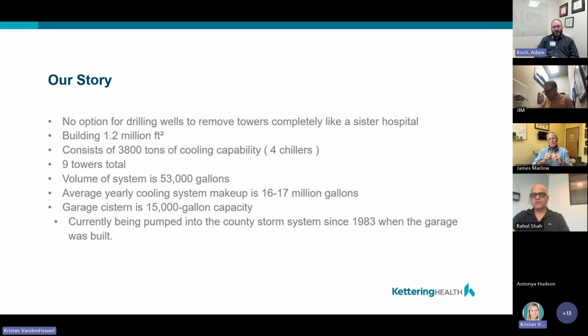We have 3800 tons of cooling capacity with 4 chillers, 9 towers total, system volume of 53,000 gallons. At the time, we were using about 16 to 17 million gallons a year just on our cooling system, not including drinking water. But that garage cistern is 15,000 gallons. When we built the garage in '83, there were pumps designed to send water out to the storm drain. So since 1983, we've been pumping water essentially away from our building.